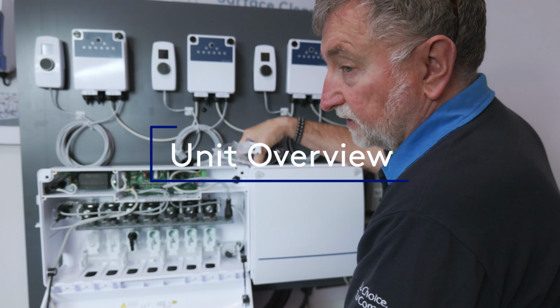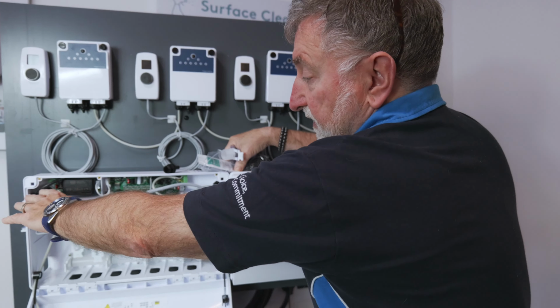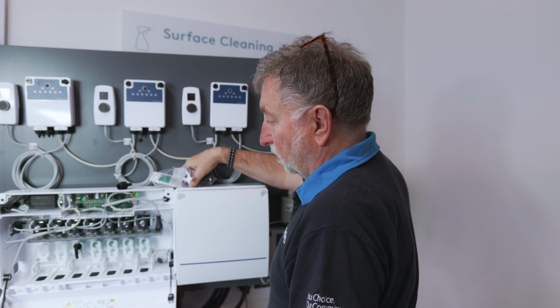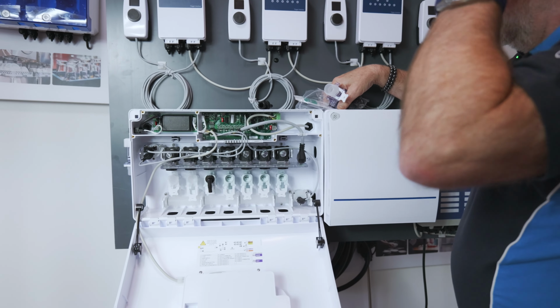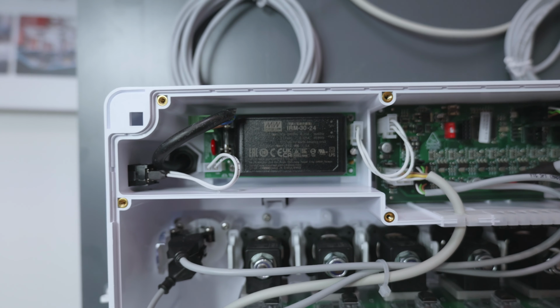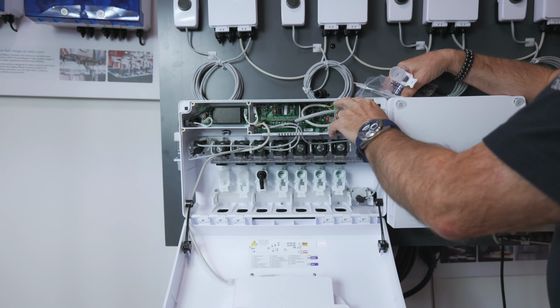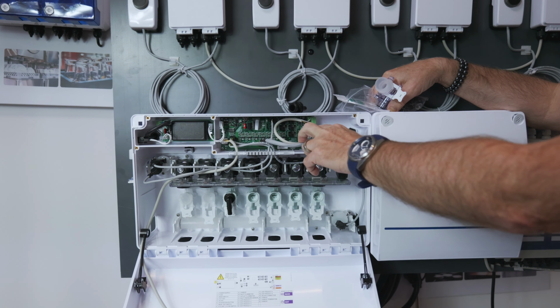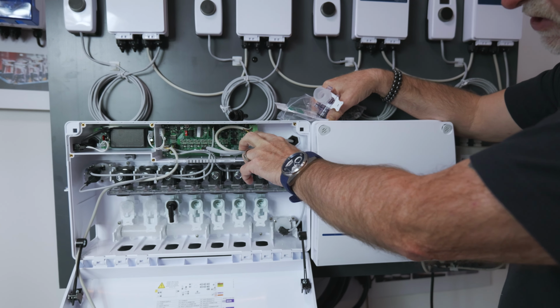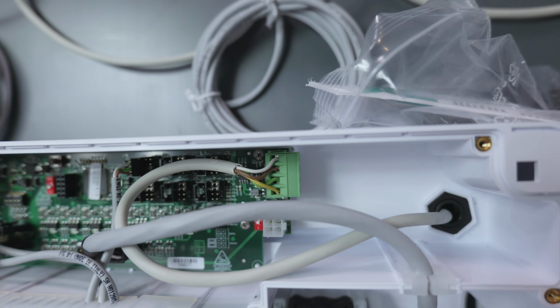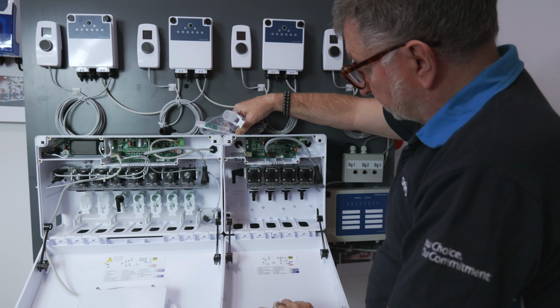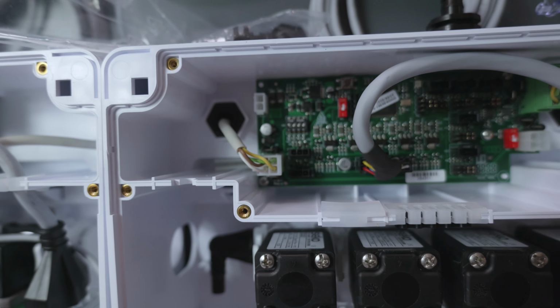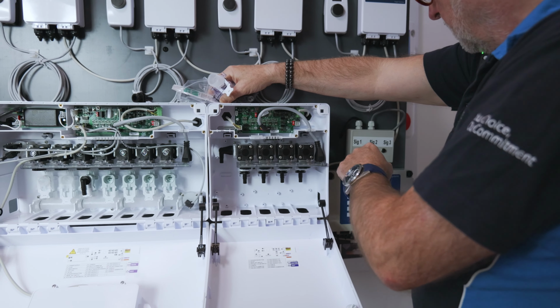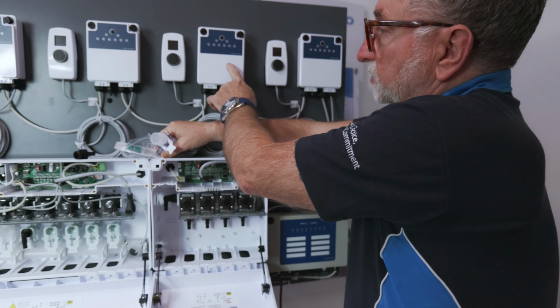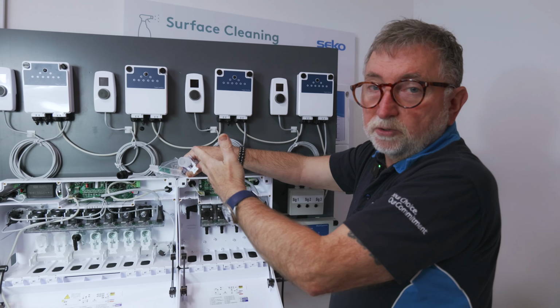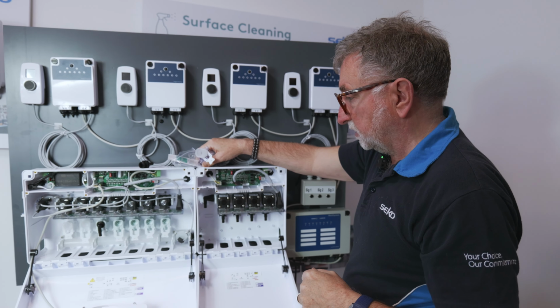Now for the purposes of this video, I've actually removed the protective cover just so you can see the wiring connections. So in here we have the mains connection, and the only other wiring you would need to do is the origin of the CAN bus connection, which is this one. This would then link to the distributor box, which I've also opened to show you, connected there, and then the outlet from there will then go to the other peripherals of the in and out, and we'll look at the internals of the signal interfaces a little bit later on.